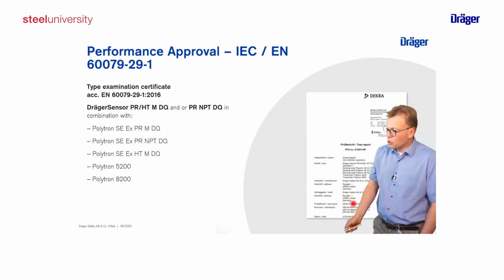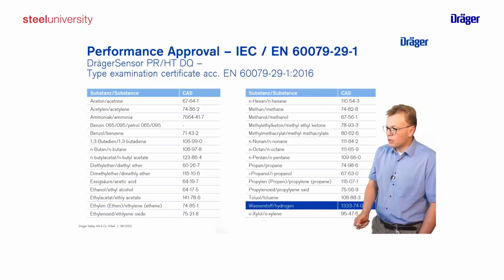So which standards were within the scope, and here we talk about measuring performance, and also which date, because when we look at standards, they always have a release date, and at a certain time you will find an update, and then you need to apply for an update of your certificate. But it's not only sufficient to have the standard listed on your certificate. It's also about, because we want to measure certain substances as primary explosion protection, that the gas which you want to detect is also part of the certificate. In this case, it's hydrogen. So if we want to use gas detectors for hydrogen detection, then I can only recommend to have a closer look at the certificates of the devices, to see if hydrogen was also tested by the notified body.